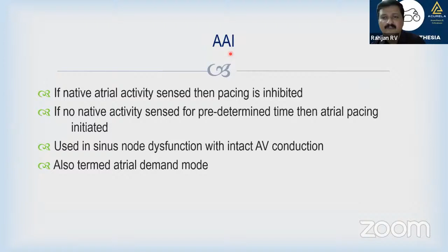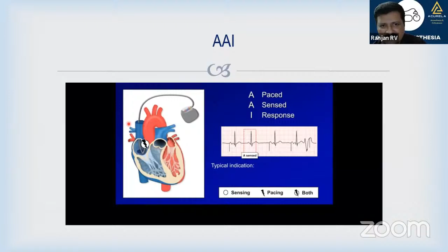I'll give you an example. Here you can see it is in AAI. Here the atrium is paced. You will set the PP duration, and that value will be added to your pacemaker. If the time interval is prolonged, that will be sensed and there is no activity, so the pacemaker will send an electrical impulse to the atrium and there will be a pacing response. Next, within a particular time, there is a native activity. So A is sensed. What will it do? It will inhibit the pacemaker from sending any electrical impulse so that the patient's native activity will continue.